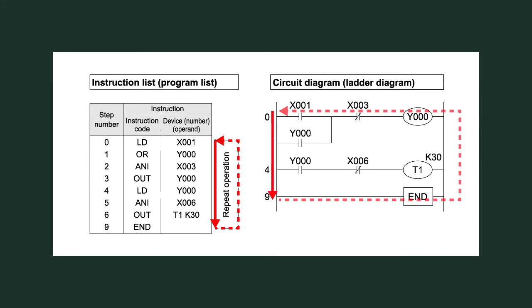Instructions are executed from step 0 to end. Then it returns to step 0 and repeats continuously. This is called cyclic execution, and the time it takes to execute step 0 to end once is called the scan time.